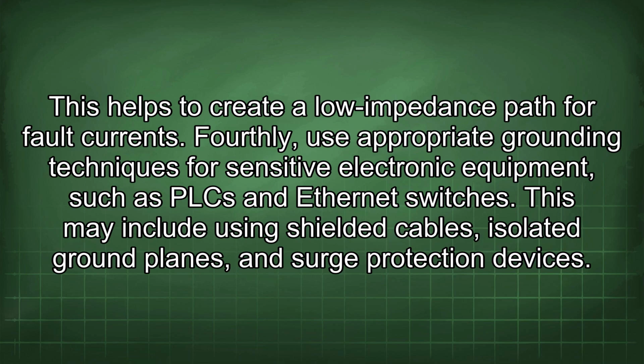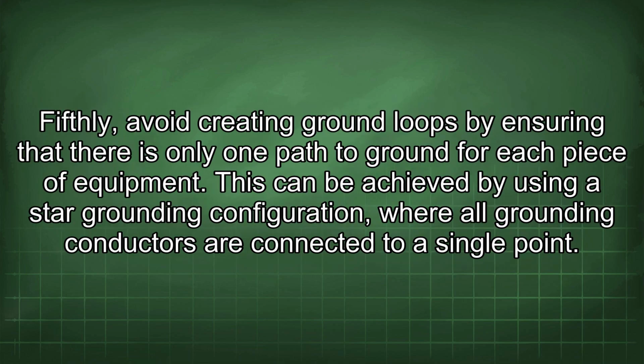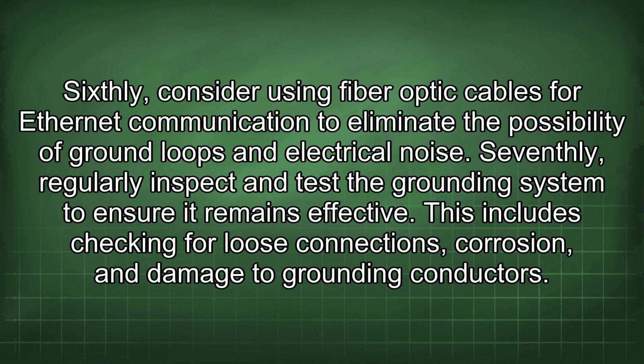This may include using shielded cables, isolated ground planes, and surge protection devices. Fifthly, avoid creating ground loops by ensuring that there is only one path to ground for each piece of equipment. This can be achieved by using a star grounding configuration, where all grounding conductors are connected to a single point. Sixthly, consider using fiber optic cables for Ethernet communication to eliminate the possibility of ground loops and electrical noise.